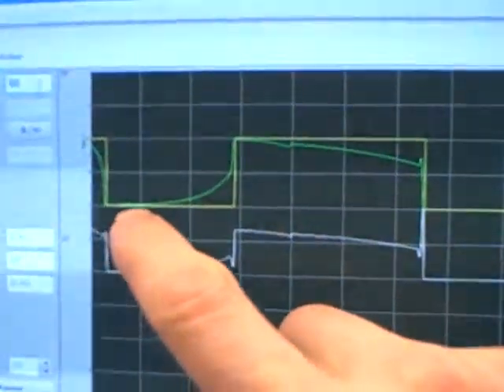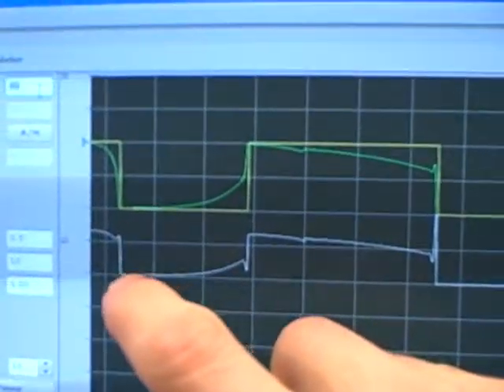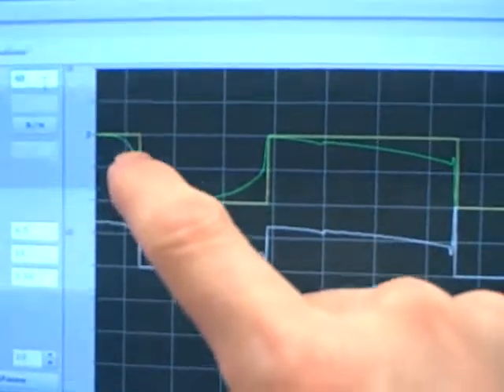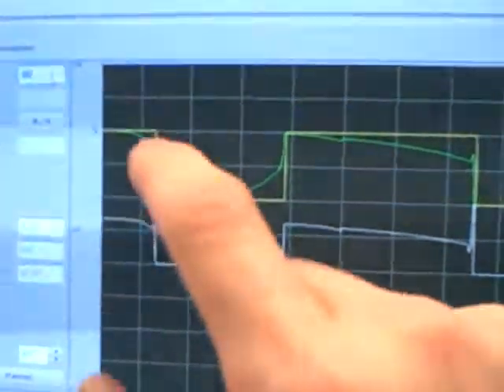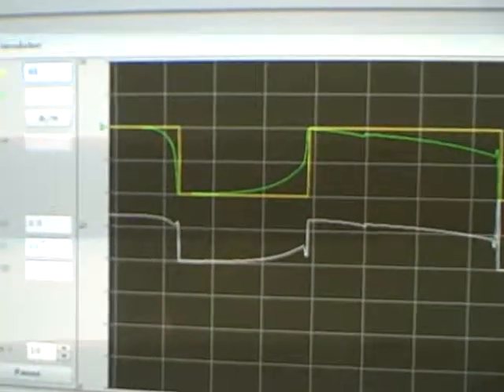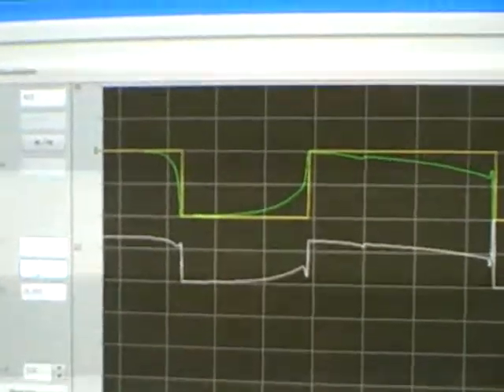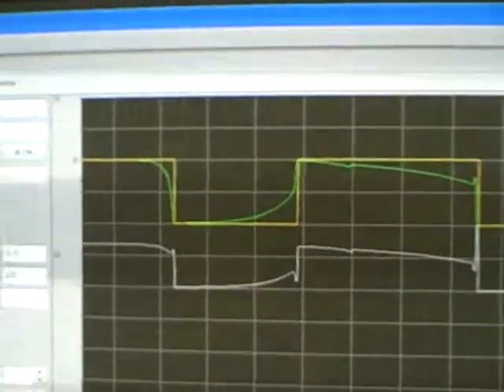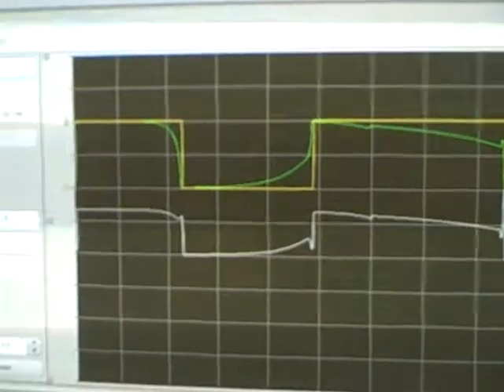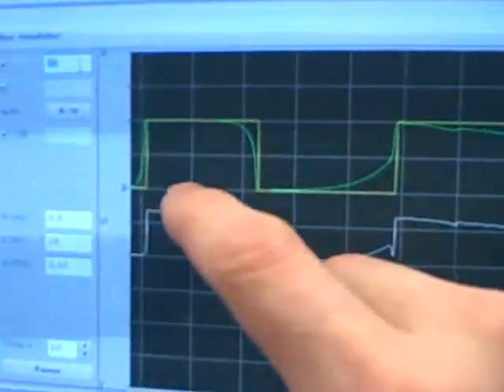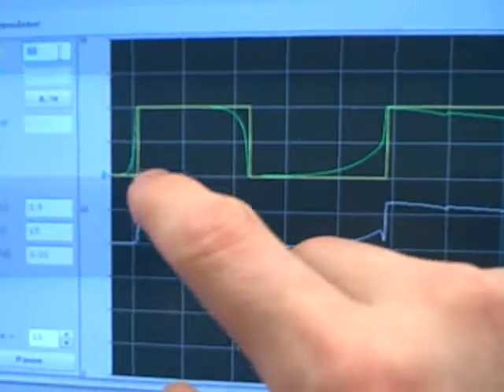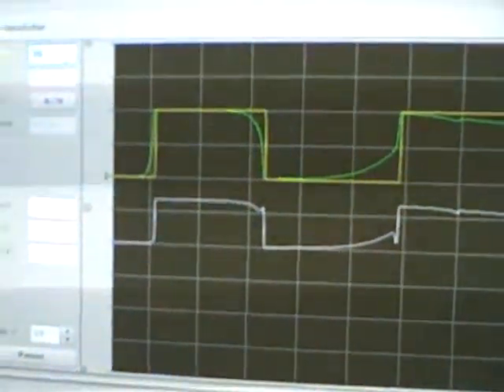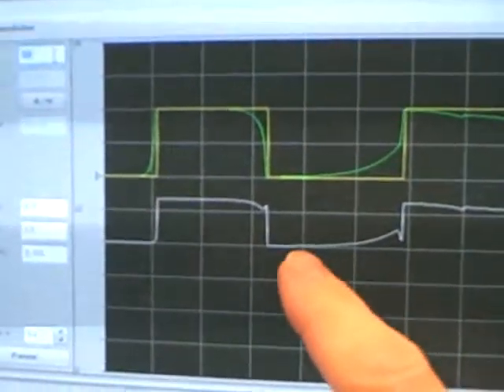There we go. Set point steps up to 40%. You can see the valve step immediately, and the process variable has a much, much faster approach to set point. We're still not overshooting, so I think we can go even more aggressive on our integral. I'm going to go to 15 repeats per minute. I'll step down to 30% on the set point, and we'll watch the response. Set point steps down. Wow, look at this. Process variable value very, very quickly reaches the new set point.